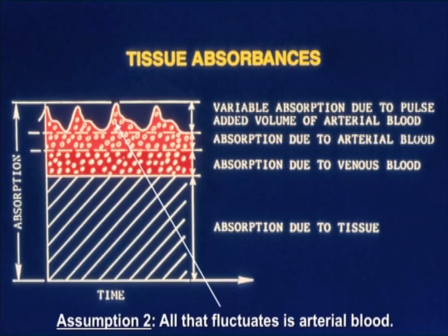And he said, aha, or eureka, however you say that in Japanese, he realized very quickly that what was pulsating was the arterial blood, the volume of the arterial blood. And that is what makes a pulse oximeter a pulse oximeter. It looks at the pulsatile component of the absorbance. And you've already seen here that I have told you assumption number 2. So remember, assumption number 1, 2 and only 2 light absorbers. Assumption number 2, everything that fluctuates or pulsates in that light absorbance signal is caused by arterial blood. Now we know that's not always true, but that's Aoyagi's assumption.